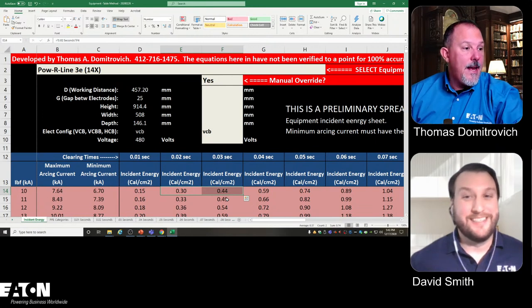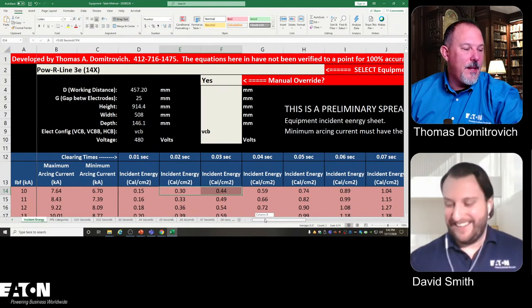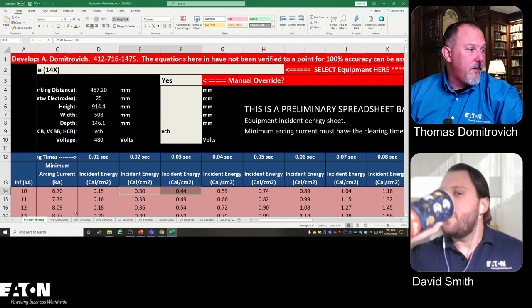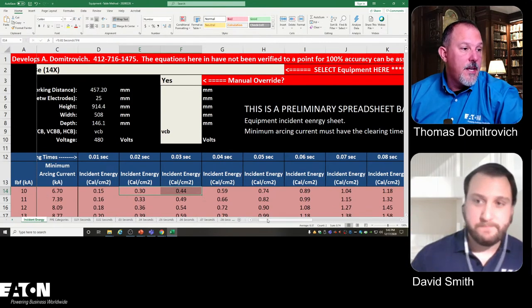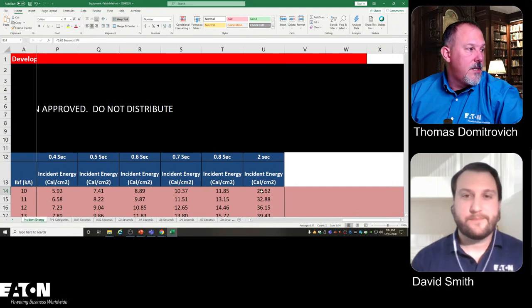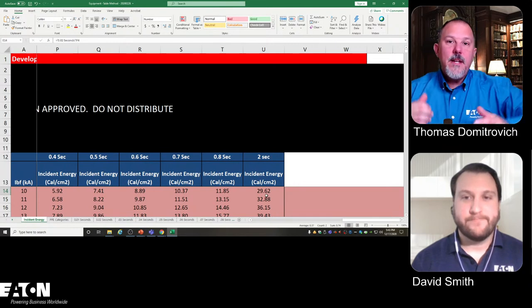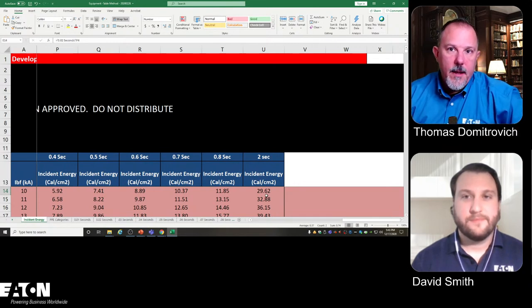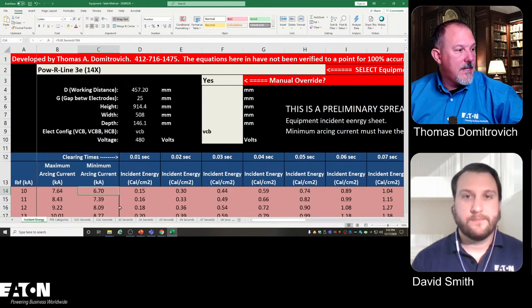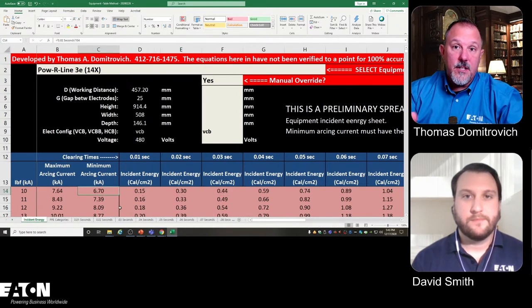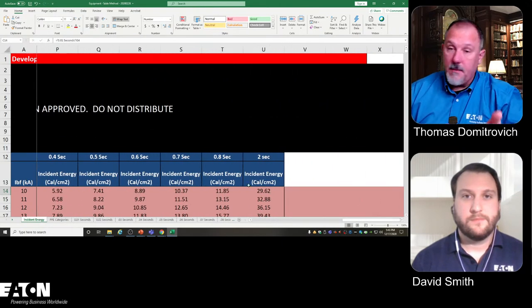Very low. You just said the calorie word, right? Now what are we talking about? I know, about PPE. Yeah, that's right, and that's going to help me. Now, if I increase, and remember, it's 10,000 amps of bolted fault current, if I increase the time to 2 seconds, I'm at 29 calories. So whether it's an 800 amp breaker, a 1200 amp breaker, a 4000 amp breaker, if I have 10,000 amps of bolted fault current, and my arcing current, my 6,700 amps, is not in the instantaneous region, then I could have a clearing time up to 2 seconds. I'm up to 30 calories.